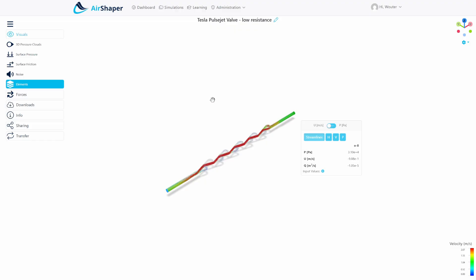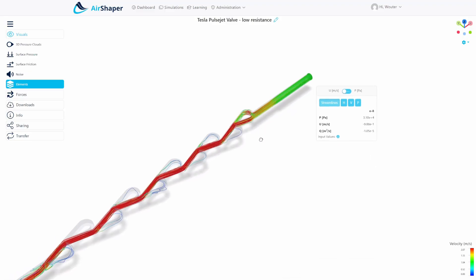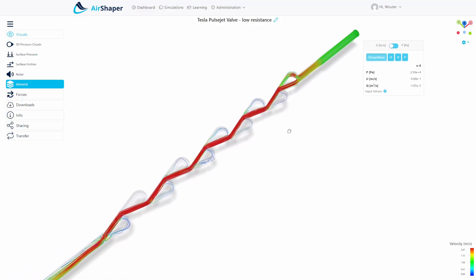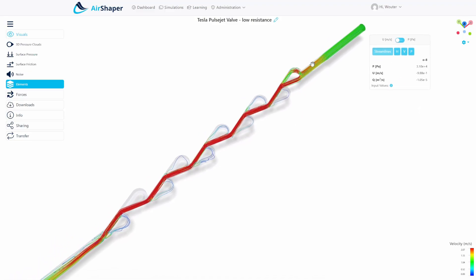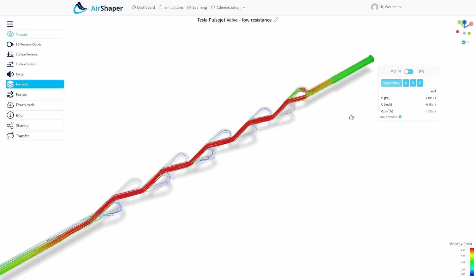These are the finished simulation results. This is the one with low pressure resistance, which means the flow starts at this end and flows all the way in this direction. You can clearly see that the flow just follows these slight bends here, bounces off the walls, and then continues straight. We have a pressure drop of 31,000 Pascals.